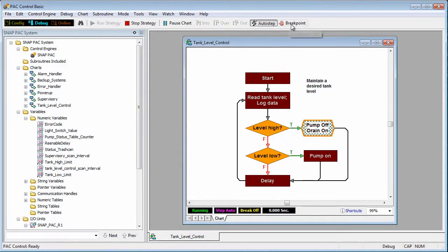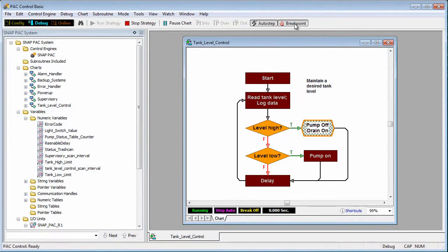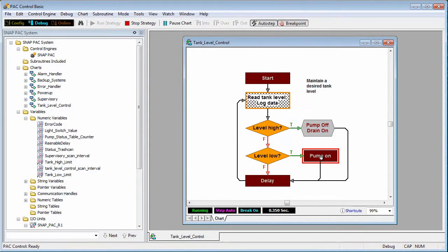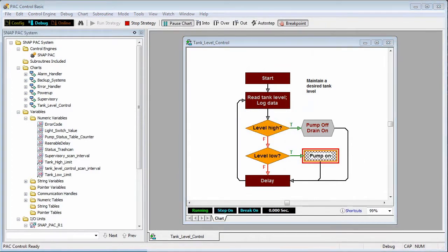You can also use a breakpoint to stop the logic at any location. Let's say that the pump isn't turning on when it should. I'll place a breakpoint to stop the logic right before the pump should turn on. PAC Control will pause right before executing the commands in that block.